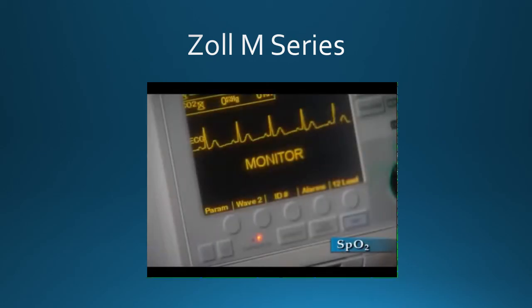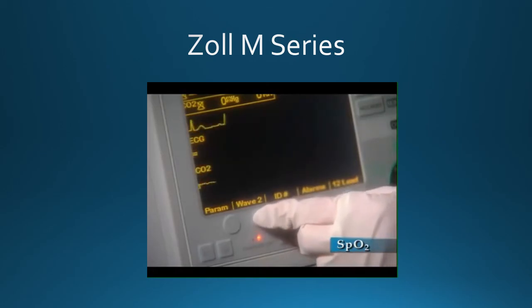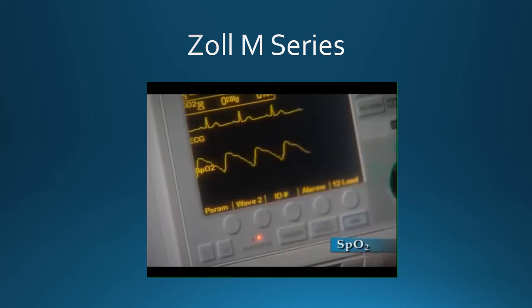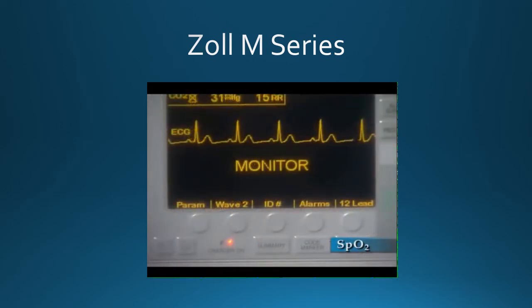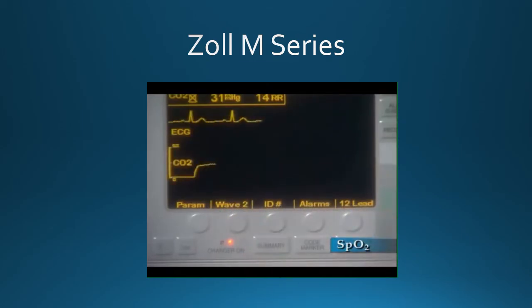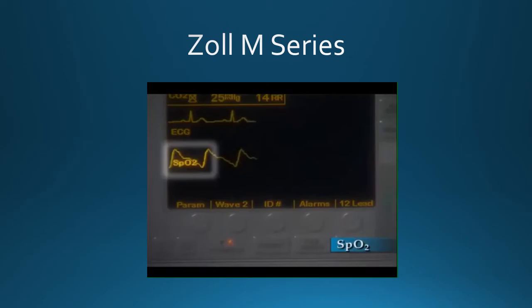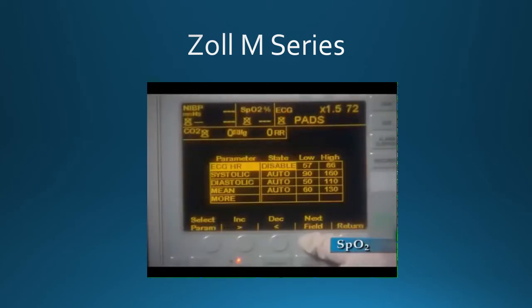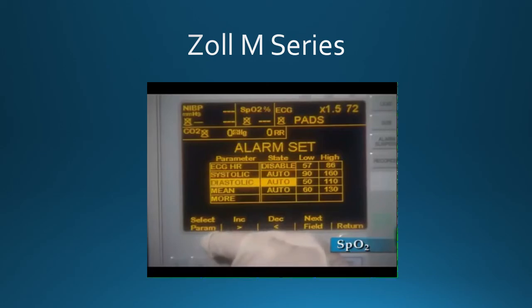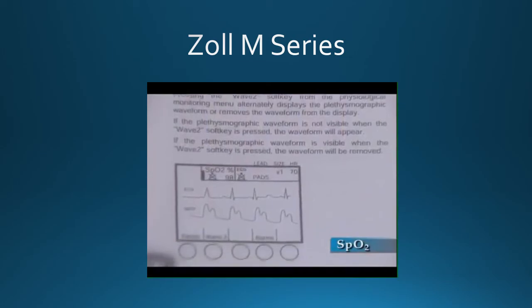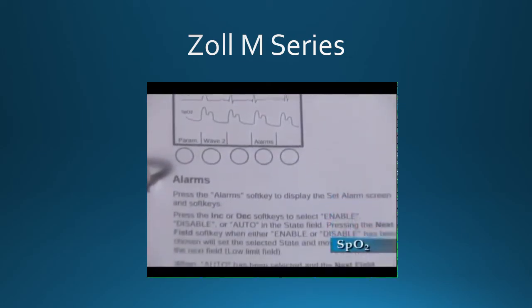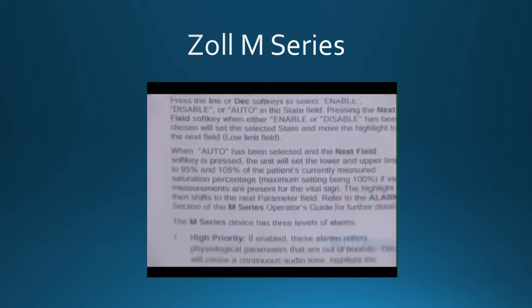If desired, the user can select a plethysmographic waveform by pressing the Wave 2 soft key until the desired waveform is displayed. If the monitor is equipped with end-tidal CO2, the ETCO2 waveform will be displayed with the first press of the Wave 2 soft key. Pressing the Wave 2 soft key again displays the SPO2 waveform. Press the Alarms soft key to display the Set Alarm screen and corresponding soft keys. This screen allows users to enable or disable alarms. Consult the Operator's Guide for detailed instructions on alarms, their priorities and limits, and how pulse oximetry operates in AEDs.